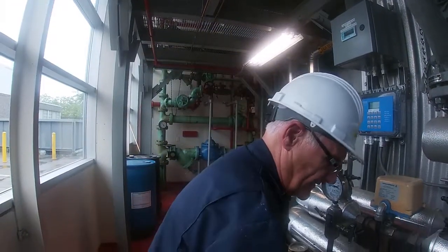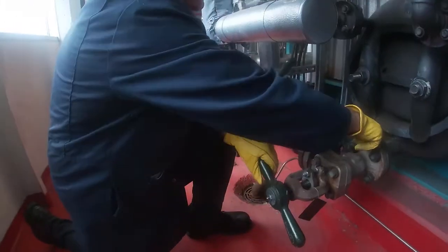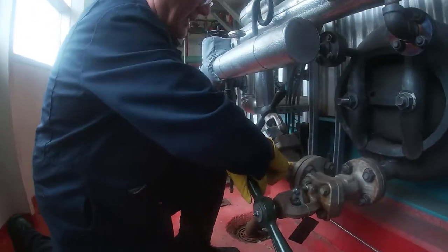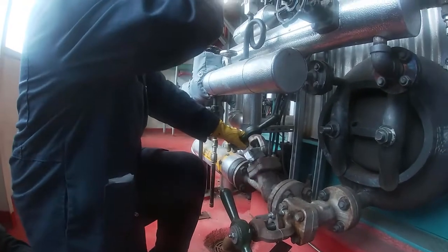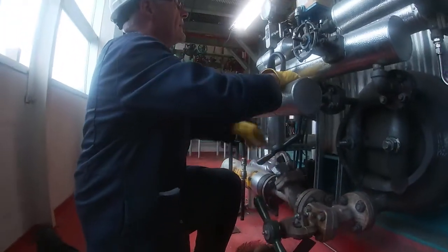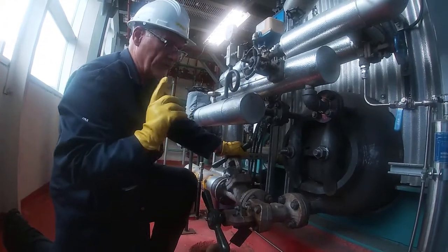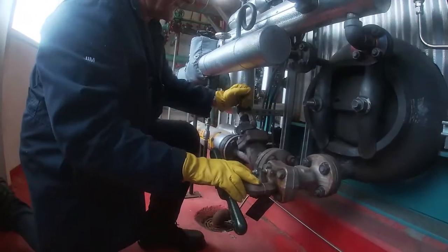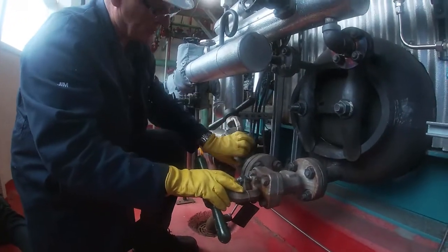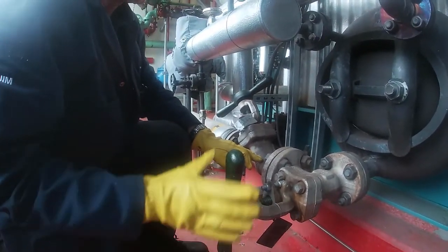So now back down to the valves. Open one. That's going to put water up to this plug. Open the second one. It's going to start blowing down. And then you're watching that water level coming down, down, down. Now, the order in which you close it is critical. You close this one first, so that plunger goes down and closes that seat. And then you close this one second.